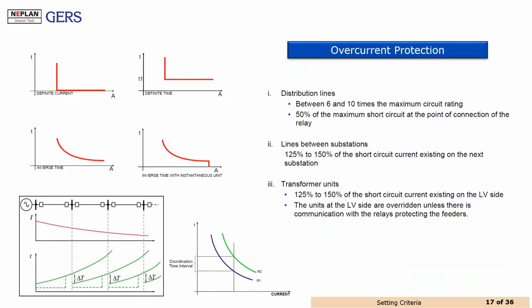To talk about the overcurrent protection, that is one of the systems that I mentioned before about selective coordination. The overcurrent protection is one of the most typical applications in protection devices. Why? Because they have different characteristics that we can coordinate. Some of them are based on specific current levels. Some of them are defined by specific time delays, inverse characteristics, or hybrids between them. I am presenting here some typical criteria for pickup setting of this kind of protection. Some of them are for distribution lines, some of them for protections between substations and for transformer units.